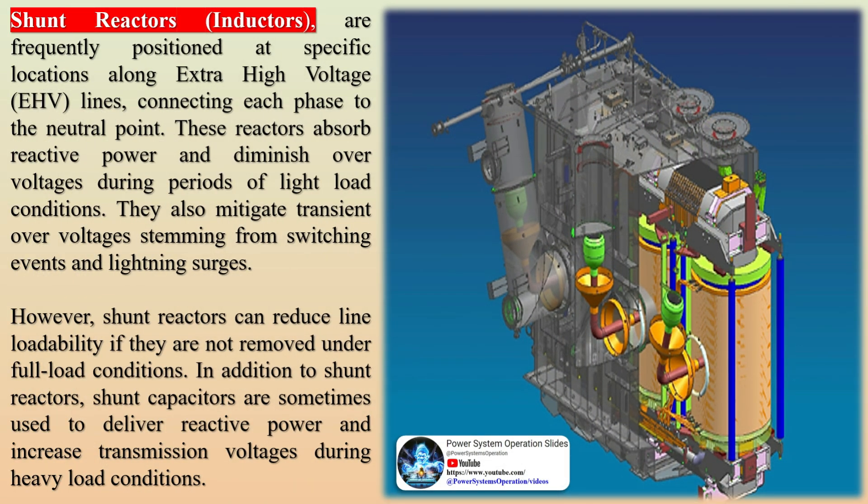These reactors absorb reactive power and diminish over-voltages during periods of light load conditions. They also mitigate transient over-voltages stemming from switching events and lightning surges. However, shunt reactors can reduce line loadability if they are not removed under full load conditions.